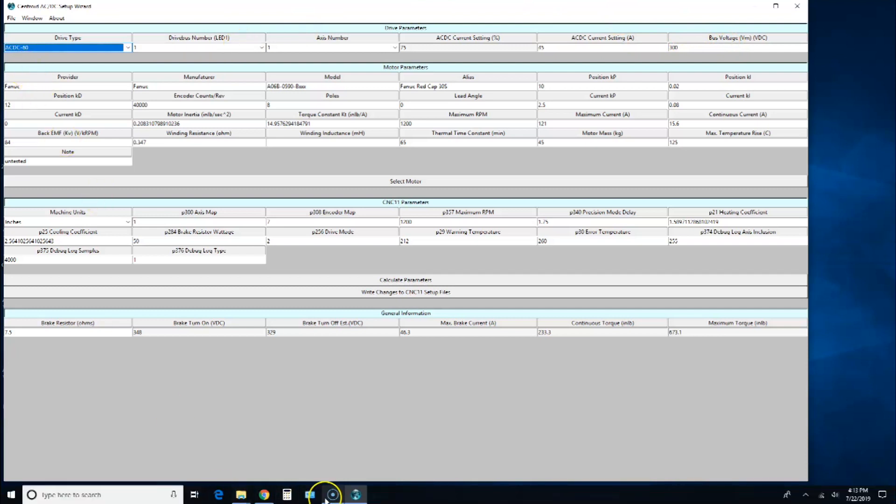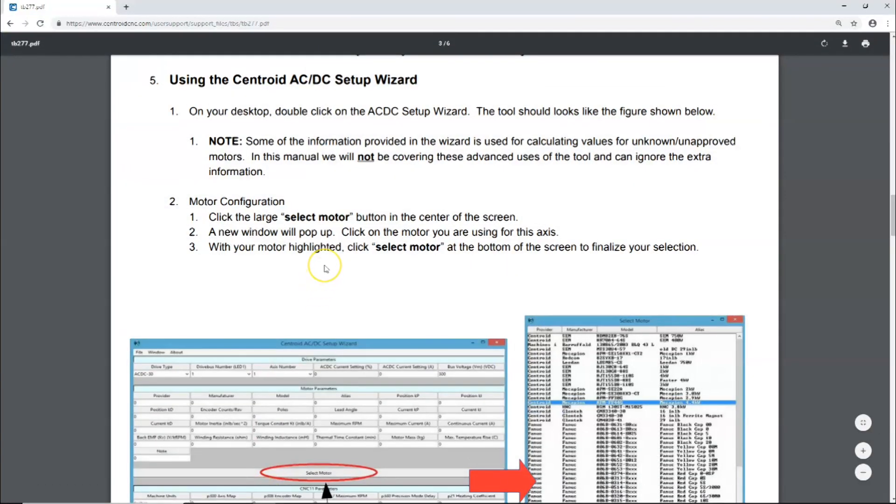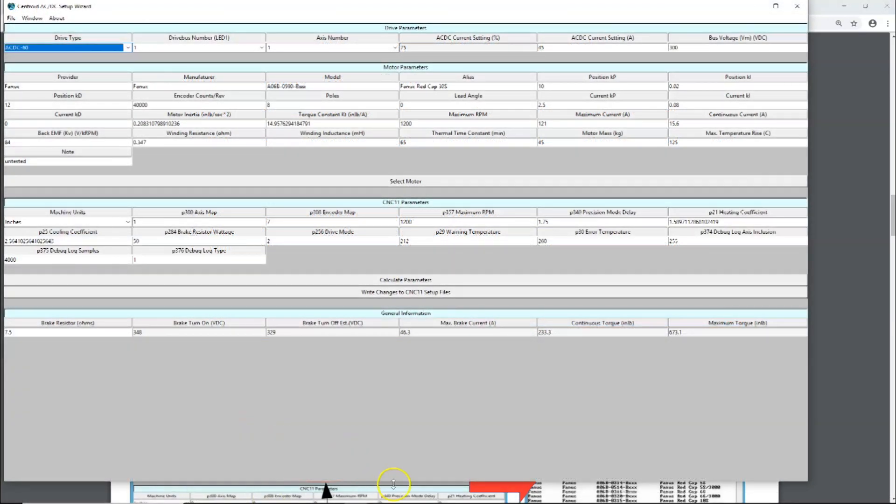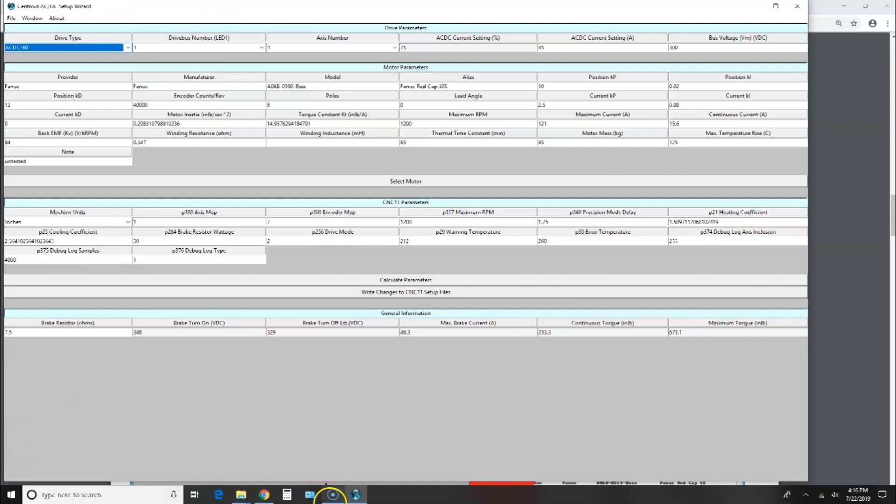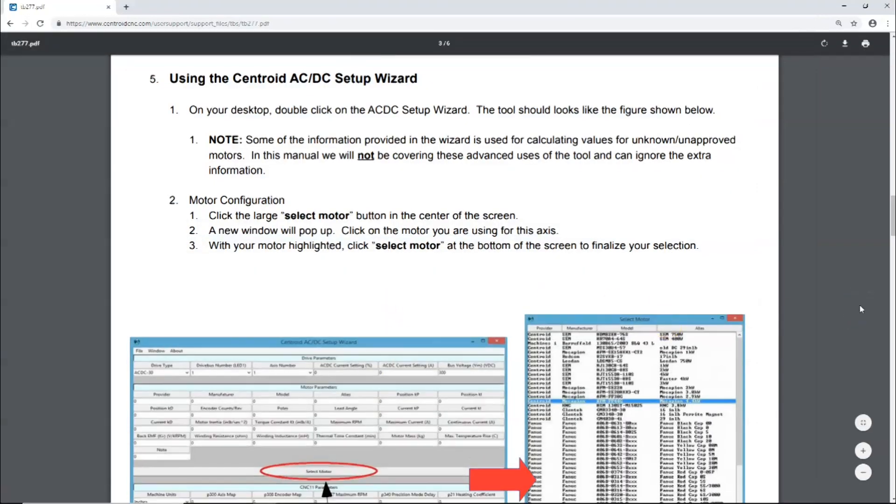Let's go to the setup wizard. It says click the large Select Motor button in the center of the screen. A new window will pop up, click on the motor you're using for this axis. With your motor highlighted, click Select Motor. It pre-populates all these parameters when you select that particular motor. These little P's are parameter 300, 308, and so forth, and it's going to populate it with these axis numbers and drive numbers. We've selected the motor.